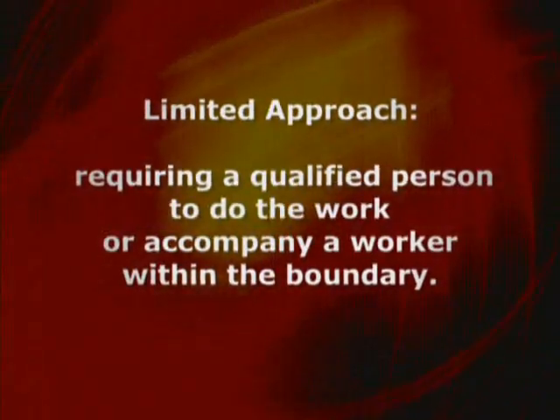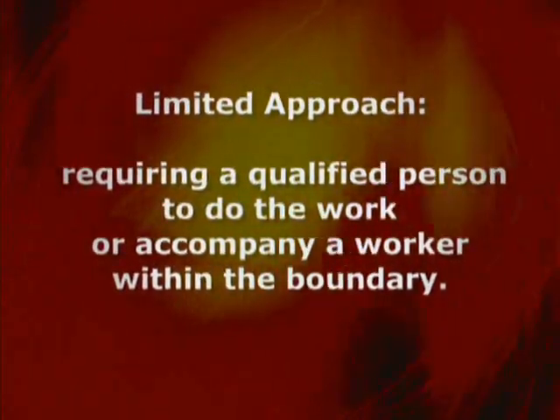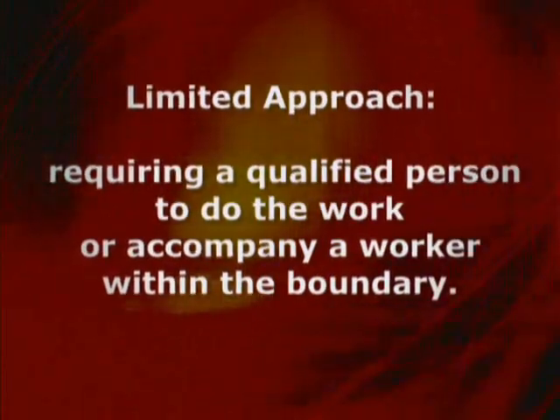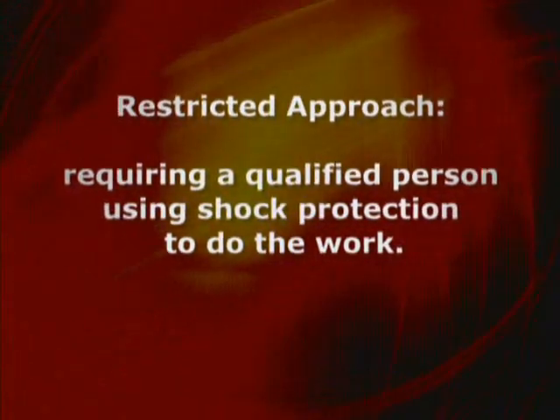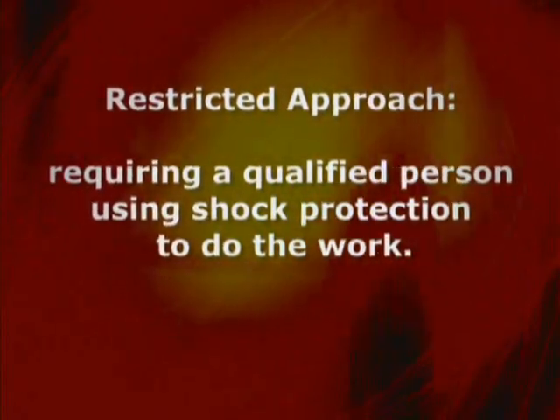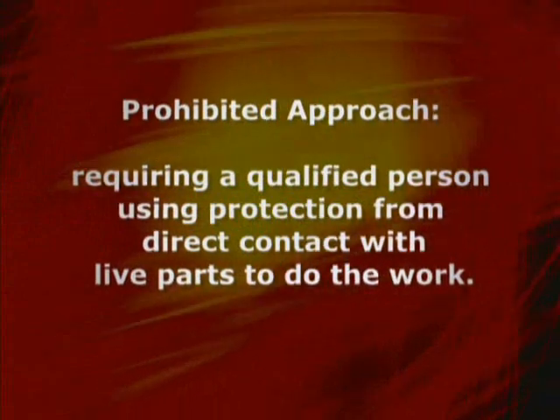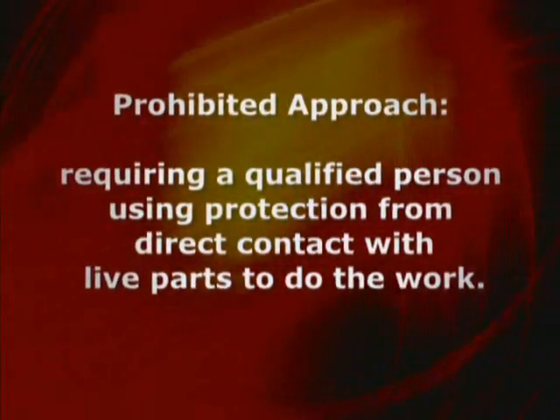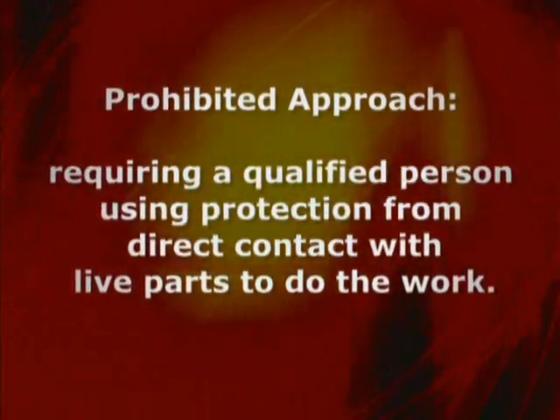An analysis of arc flash energy information is critical for determining safe work practices. Boundaries should be defined as limited approach, requiring a qualified person to do the work or accompany a worker within the boundary; restricted approach, requiring a qualified person using shock protection to do the work; and prohibited approach, requiring a qualified person using protection from direct contact with live parts to do the work.